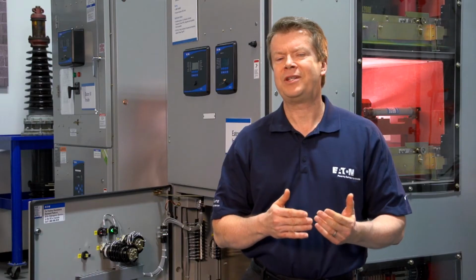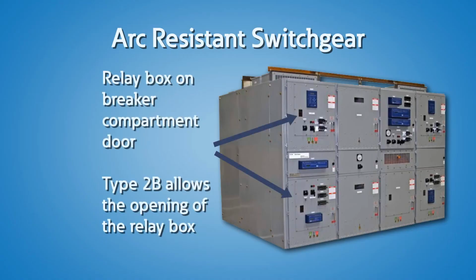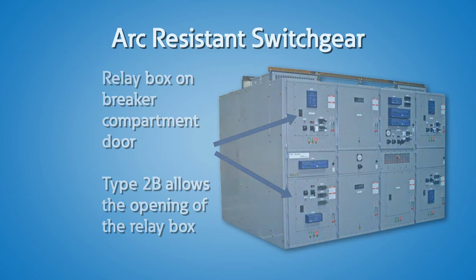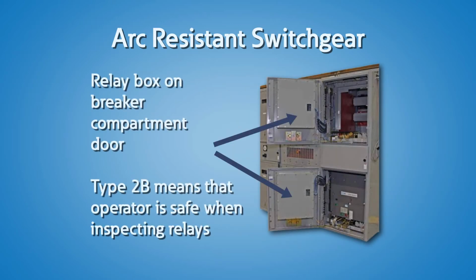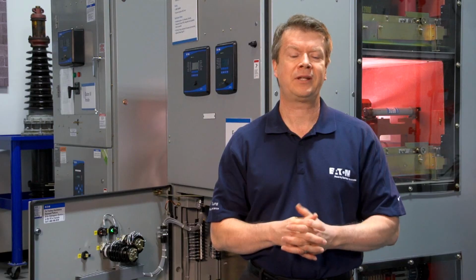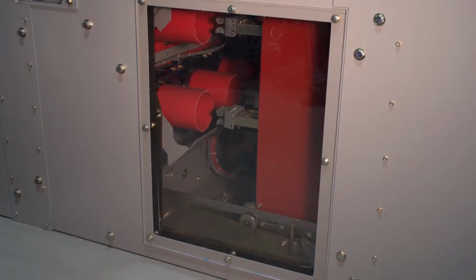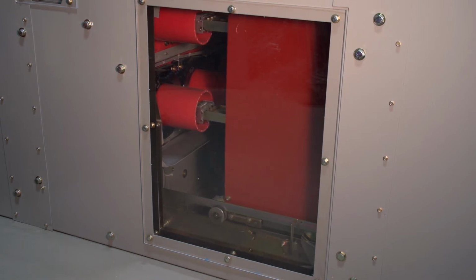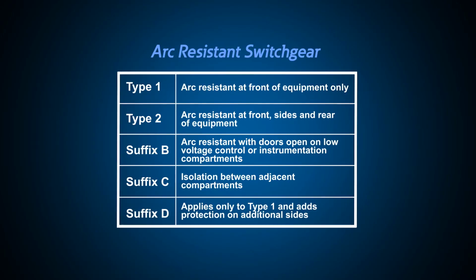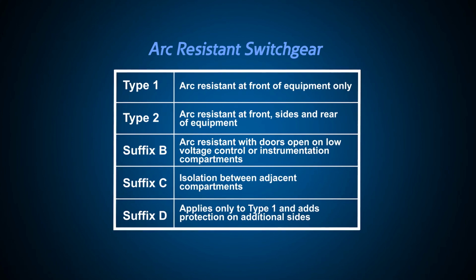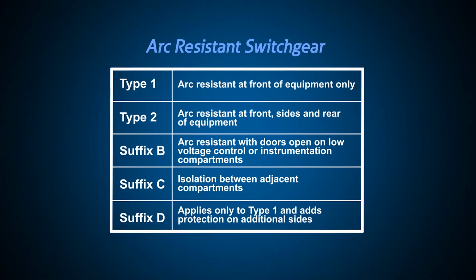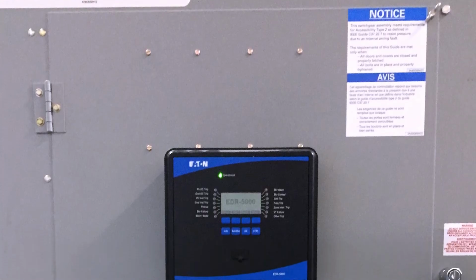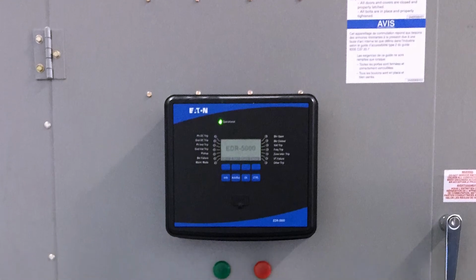This gear is built with additional reinforcements in the structure of the gear and the doors to maintain its integrity during arcing events. The idea with this gear is to do everything with the door shut, like this self-racking mechanism in our medium voltage arc resistant switchgear. The most common type of arc resistant switchgear is type 2B. With 2B medium voltage arc resistant gear, the low voltage metering, relaying, and control compartments are isolated from the gear with a separate door.